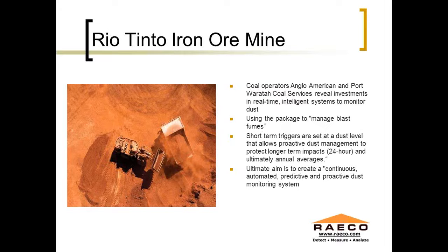So in this case, and what we see a lot, you've got a 24-hour monitoring station set up all around this mine. They do a lot of blasting. They're looking at annual averages, and they're also looking at short-term 15-minute averages specifically during the blasting. If an excursion happens, they can go in and take some kind of engineering action. It might be a spray down with potable water. It might be increasing some of the ventilation controls they have in place.